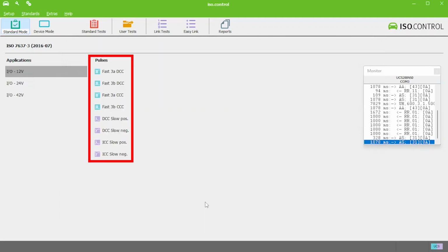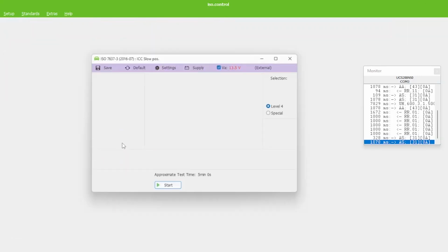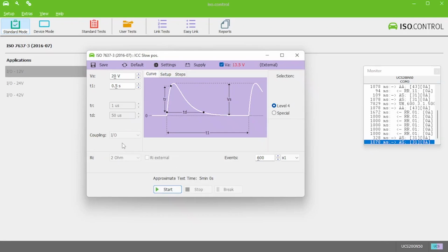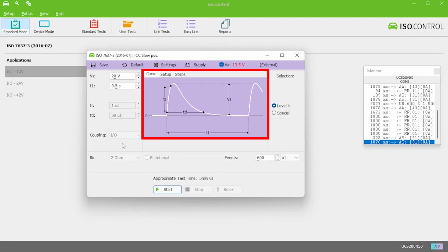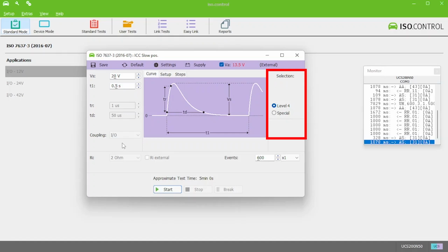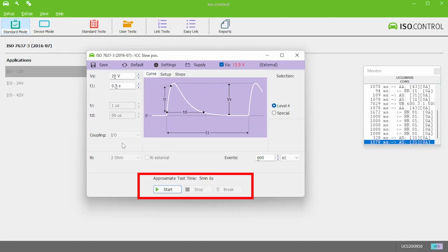As you can see, we have the different pulses here, as well as the associated test methods. We have our DCC and CCC at the top using the fast pulses, and below that we have the DCC and our ICC methods with the slow pulses. Let's take a look at the slow pulses using the ICC method. As you can see, we have our test pop-up here, with the test criteria along the left, a graphic representation in the middle, and our level on the right. All the way at the bottom of the menu, we have our Start button.